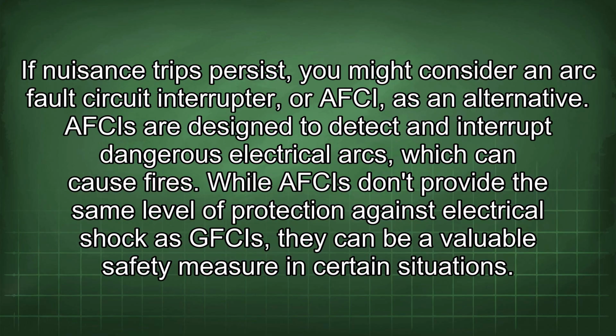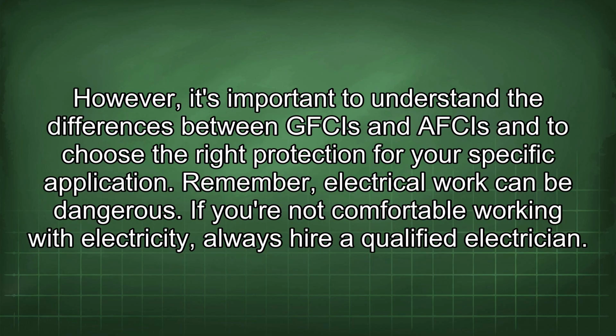If nuisance trips persist, you might consider an arc fault circuit interrupter, or AFCI, as an alternative. AFCIs are designed to detect and interrupt dangerous electrical arcs, which can cause fires. While AFCIs don't provide the same level of protection against electrical shock as GFCIs, they can be a valuable safety measure in certain situations. However, it's important to understand the differences between AFCIs and GFCIs and to choose the right protection for your specific application.